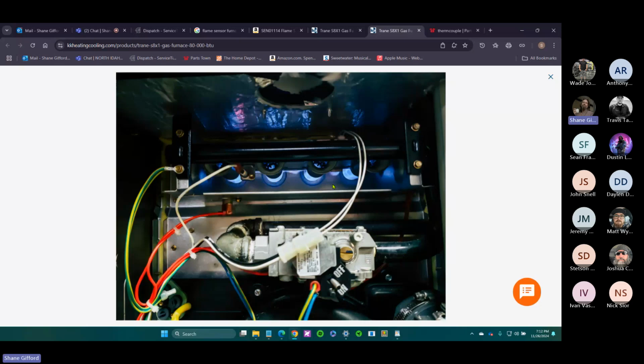A failed igniter or a weak electrode or a gas appliance that's failing to ignite, usually the lockout is 3 times. If we have a failed ignition 3 times in a row, now it's going into a hard lockout, and until you reset power, it will not run, because you don't want this whole area filling up with gas and then, whoopsie, all of a sudden 15 tries later it decides to ignite. You just created a bomb. Has anybody lit a gas grill with the lid down?